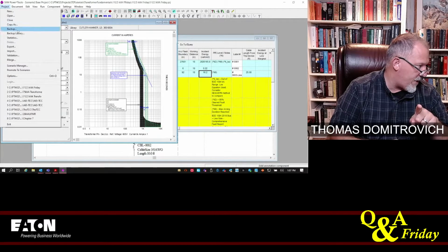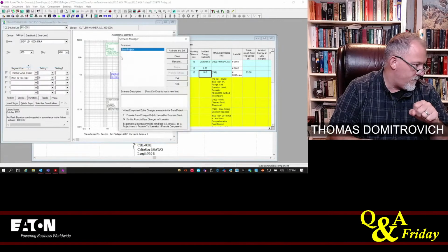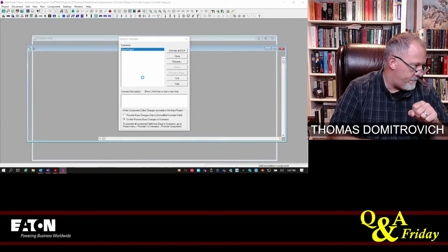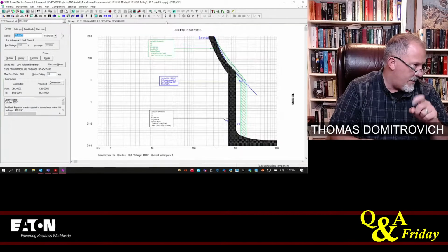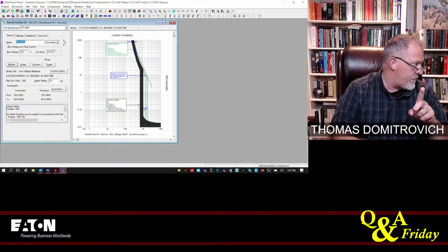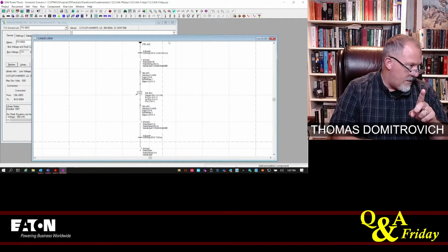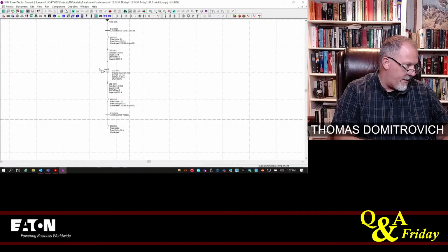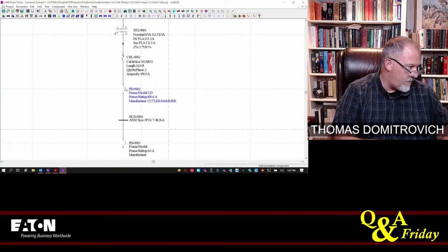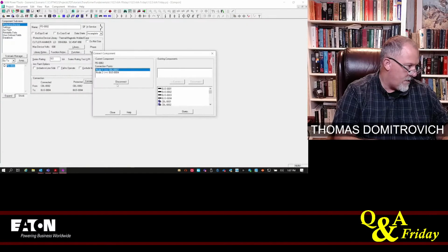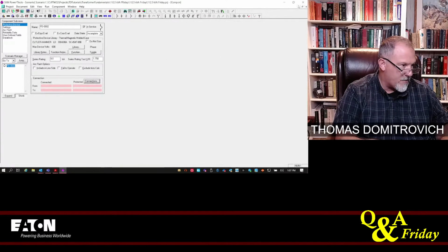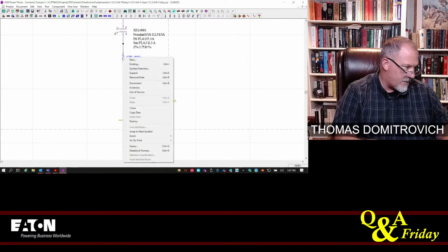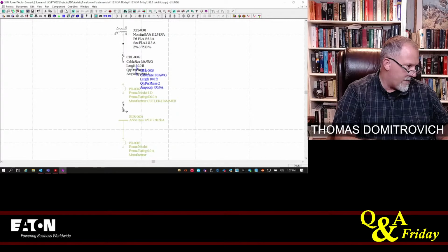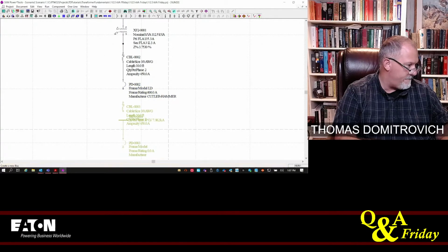Now, let's run a scenario. We're going to go project, scenario manager. I'm going to clone it. And then I'm going to activate the clone. So now, back to the one line, I'm going to make a small change on the secondary. I'm going to disconnect the primary and secondary so that breaker is by itself. I'm going to clone this conductor, put that on the secondary. I'm going to connect that breaker to that conductor, and I'm going to put a bus in between.